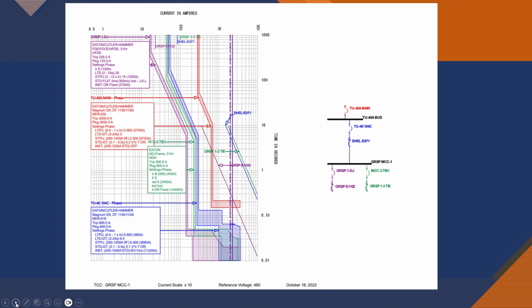Coordination in this example is not mandatory per the NEC, but it was elected by the facility owners for the continuity of service. I think this is a water facility in Commerce City. They didn't need to do selective coordination, but they sure wanted to maintain continuity of service there. So this example is just to confirm the separation of trip curves for times beyond 0.1 second, and it would therefore comply with 517.31(G).